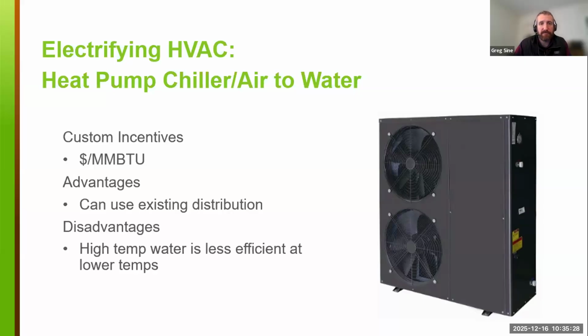There are a number of advantages to it. There's reduced refrigerant within the living spaces. That's a safety concern, and it's eliminated through use of an air to water heat pump. And it can sometimes be more of a drop-in type solution to your existing system, as opposed to air source heat pumps or VRF, where you'd be installing an entirely new system in most cases.